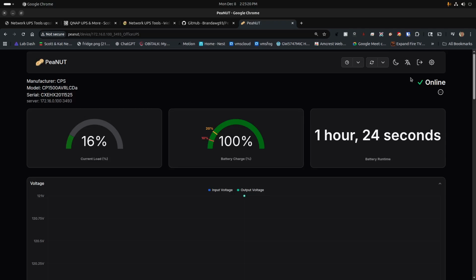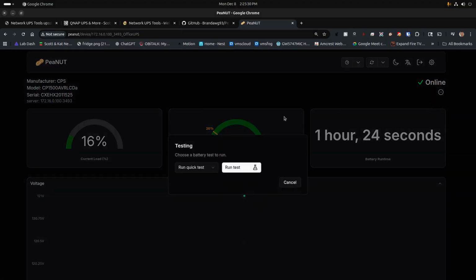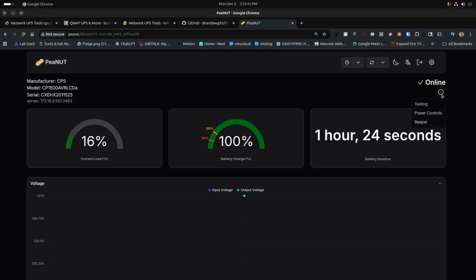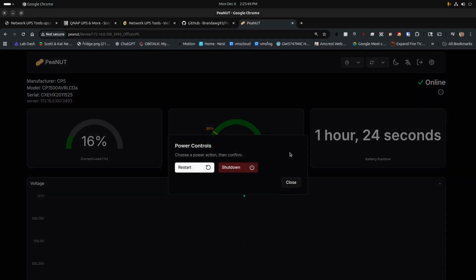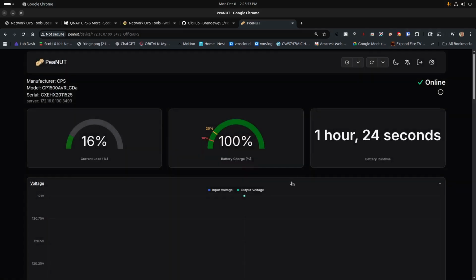Now, if I come back up here, there's a very small section here where it says actions, and it gives me the ability to do some testing. So I can go off and do a quick test or a deep test of that particular UPS unit. The other thing that I can do here is control the power, where I can decide to either restart or shut down that UPS unit.